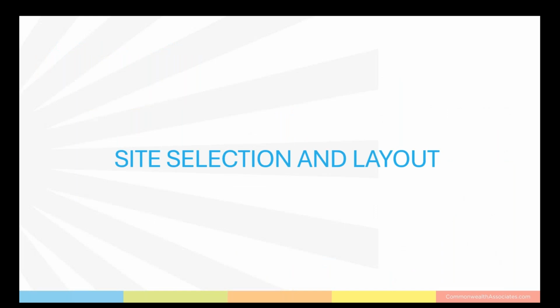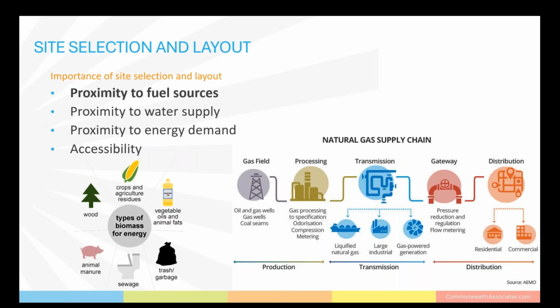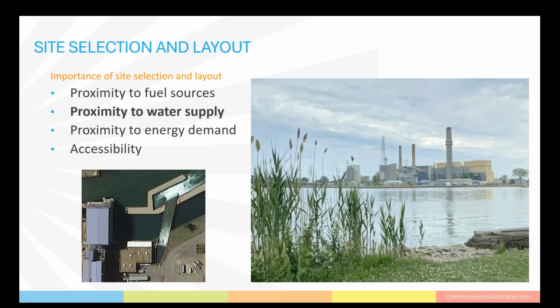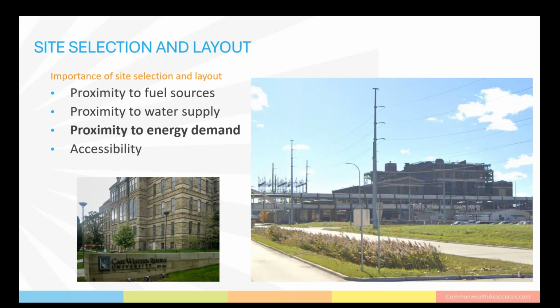So I'll start with some considerations relating to the site. And typically the client already has a site in mind and have already headed down the path that a CHP is the best option for their specific needs. Some of the factors that will drive major and ancillary equipment needed are proximity to fuel source. Typically, we would see natural gas as the source, but there are other biomass options such as wood pulp or crop residue, for example, in a CHP with boilers as the heat source. Proximity to water. The geographic location of the power plant is a huge impact on cooling technology options and therefore the equipment required. Proximity to energy demand, for example, industrial processes, commercial buildings, or the electrical sector.